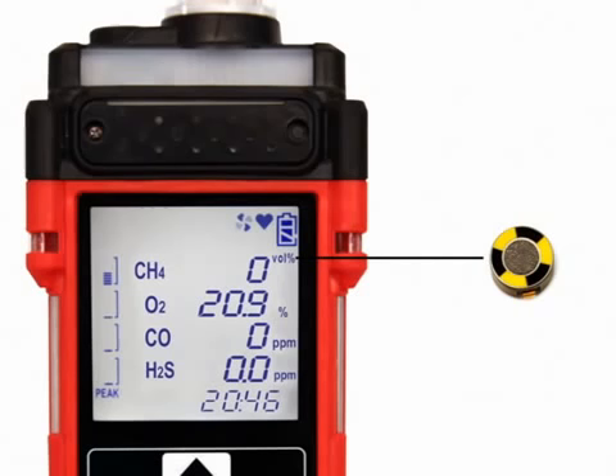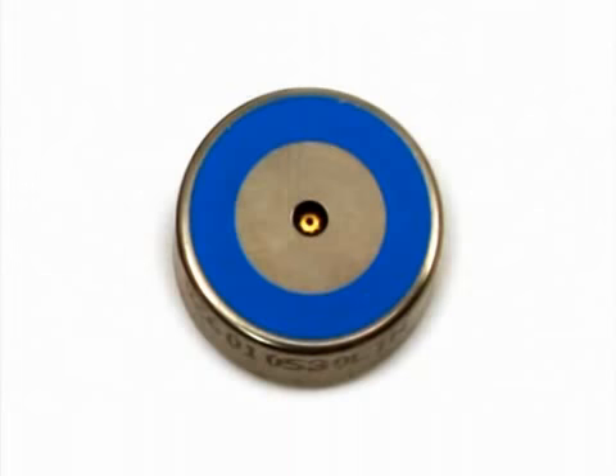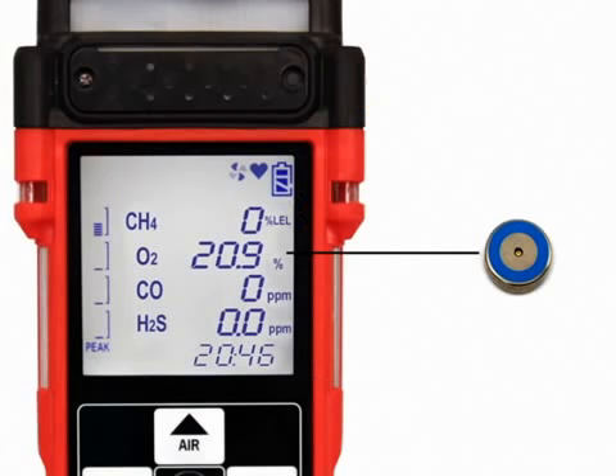the LCD. The oxygen sensor is a galvanic type sensor. A membrane covers the cell and allows gas to diffuse into the cell at a rate proportional to the partial pressure of oxygen. The oxygen reacts in the cell and produces a voltage proportional to the concentration of oxygen.